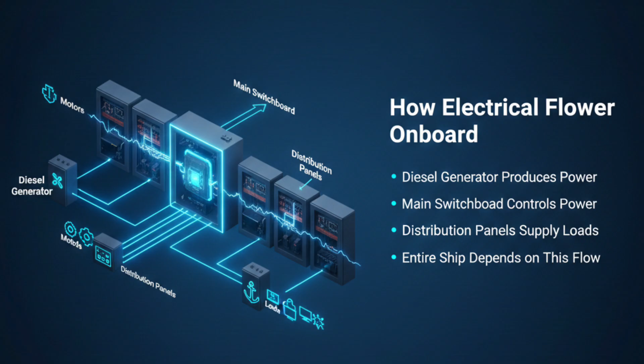Marine diesel generator. Now let us briefly understand the marine diesel generator. This generator produces three-phase AC power. On most ships, the voltage is either 440 volts or 690 volts. Frequency is usually 60 Hz. The generator has two very important control systems. First is the AVR, or automatic voltage regulator. It controls the output voltage. Second is the governor. It controls the engine speed, which directly controls frequency.